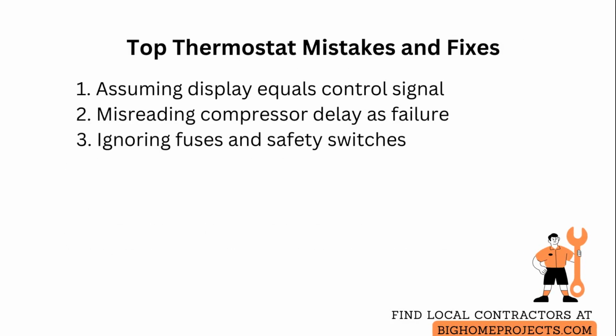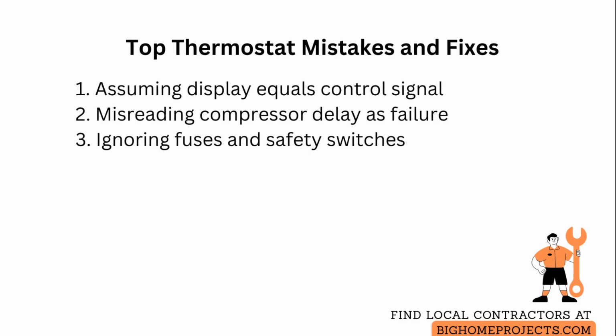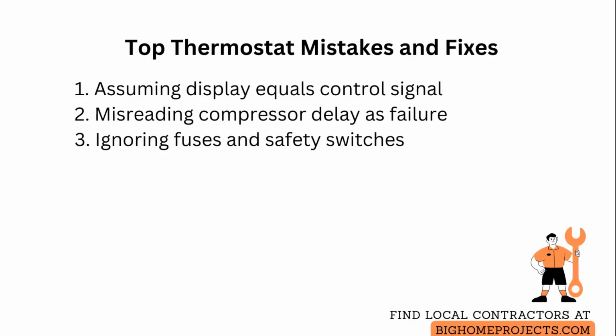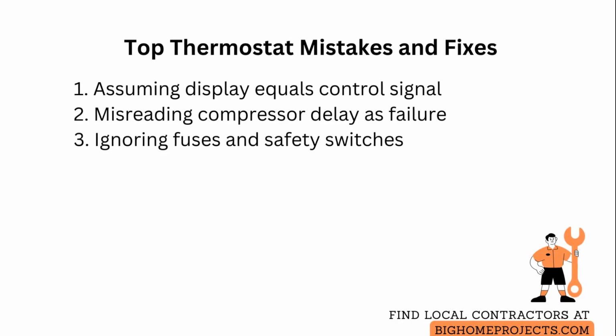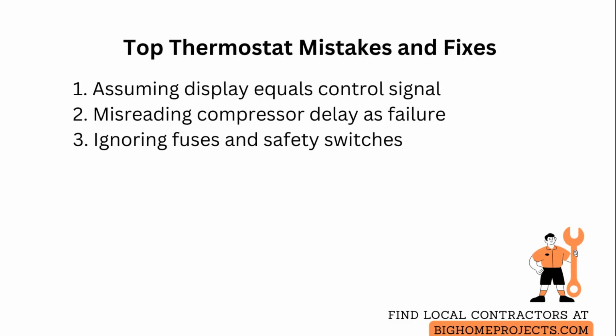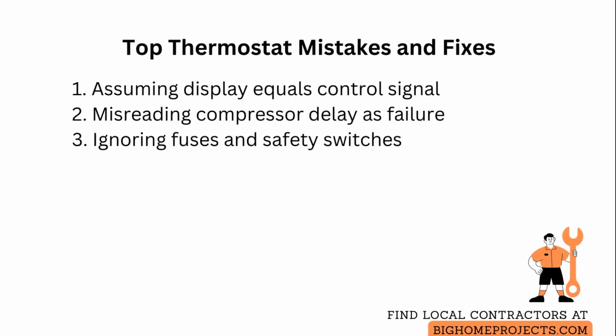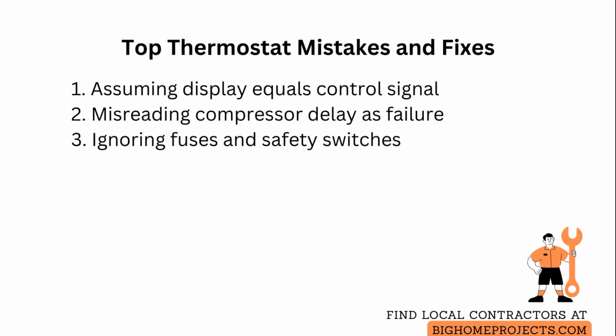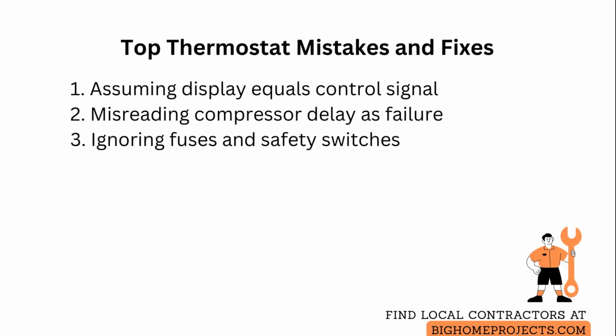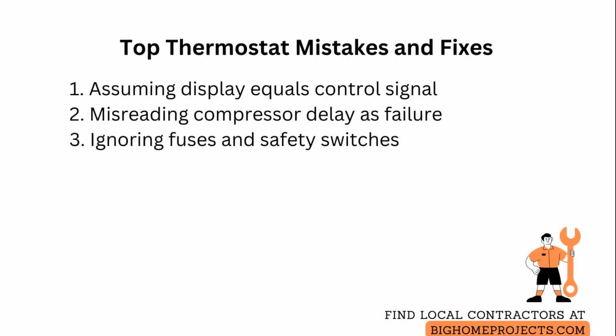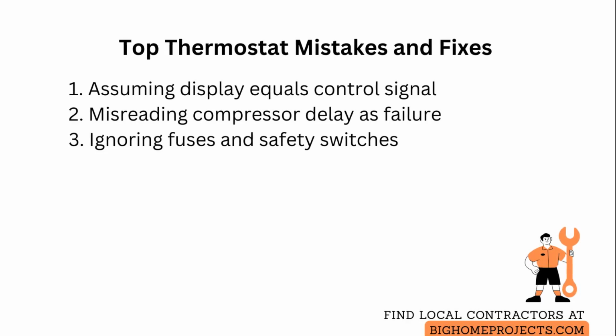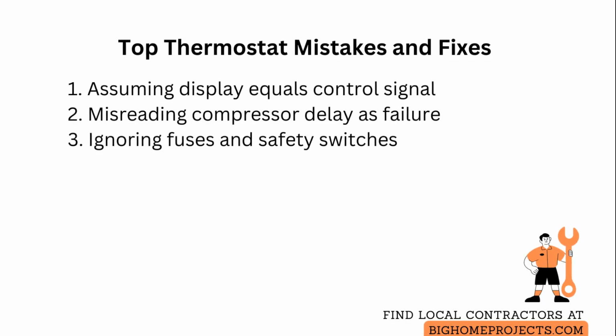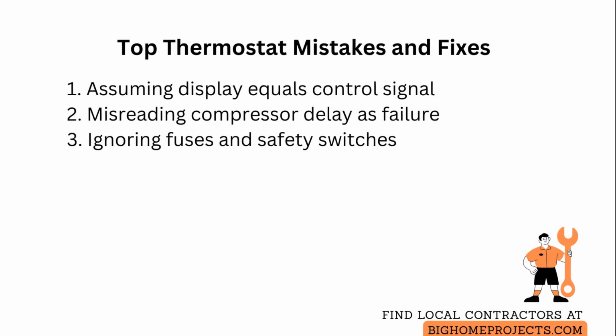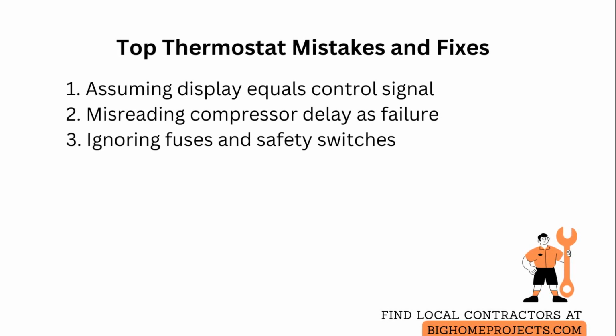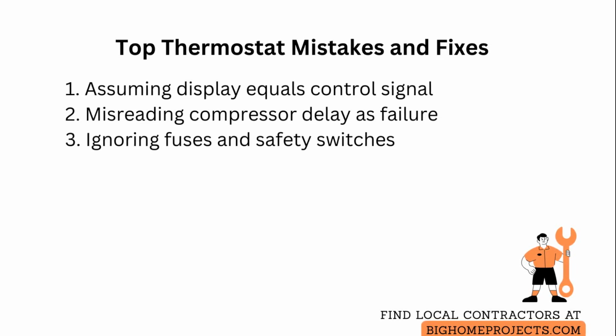3 frequent mistakes are assuming the thermostat display equals a valid control signal, misinterpreting normal compressor delay as equipment failure, and neglecting to check control fuses or door switches. Fix the first by confirming a voltage call at the control board. Fix the second by waiting out the 5-minute interlock and verifying calls during a deliberate mode change. And fix the third by visually inspecting and testing fuses and safety interlocks before replacing major components.